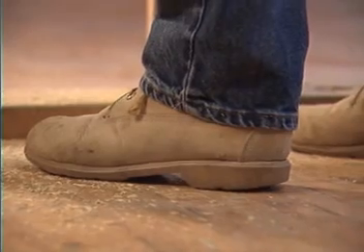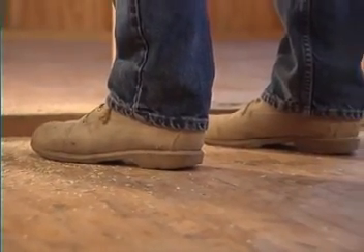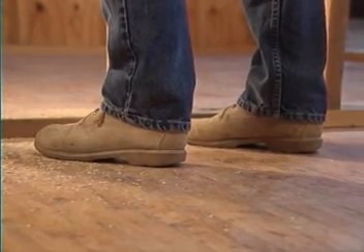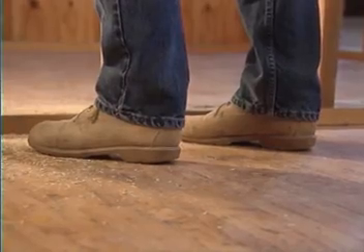Dry rubber sole shoes help reduce the chance of current flowing through your feet to ground. These shoes should be worn around electronic, electrical, and industrial equipment where a shock hazard is possible. But don't let the shoes give you a false sense of security. They can never act as an insulator. Current flowing in one hand, across your chest, and out the other hand wouldn't be affected by rubber sole shoes. Shoes are an important safety precaution, but they will not prevent current from flowing through your body.